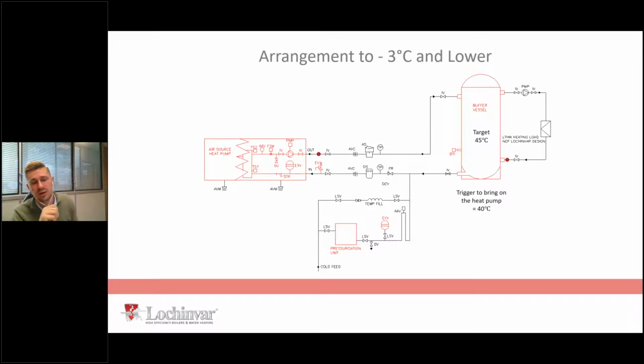So just be conscious of that when you're looking at any heating system. You'll have space in the plant room for that. And what that does is it allows the heat pump to operate and bring on some compressors. And when the compressors come on, you want to keep them on and keep them running. If you drop those compressors out too quickly, the heat pump cycles. And turning on a heat pump, a bit like turning on a circulating pump, it's a very current drawing, energy consuming process. So you consume all that energy getting it going, and then it gets nice and efficient and runs nice and effectively for a long period of time. That's what the 10 litres a kilowatt will give you the ability to do.